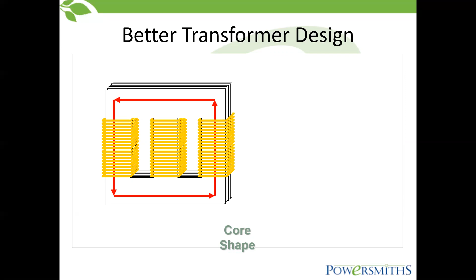They've got a core shape like this, where the current being flown through the transformer is actually bumping up against resistance at every corner. So it's going to create losses, resistance, which creates losses, which creates heat. Where we come about, we're putting almost a miter - we're using miter joints. So now the resistance is less, a little taller core, but resistance is less, and you're going to have less losses in the core than the eddy current losses and the I squared R losses.